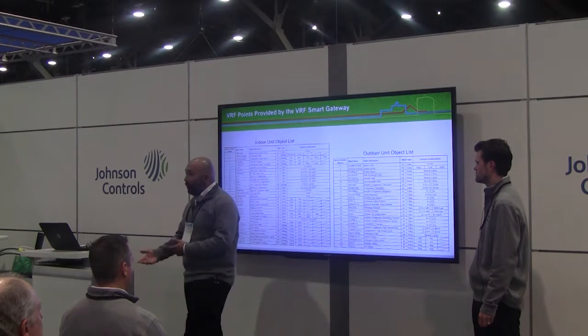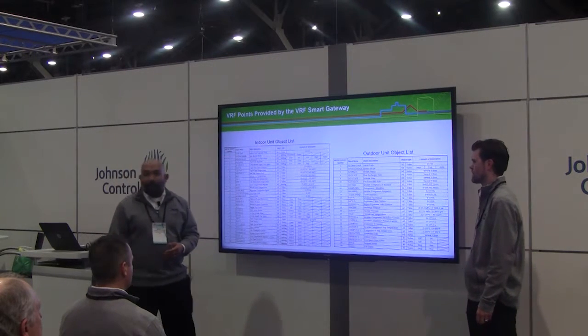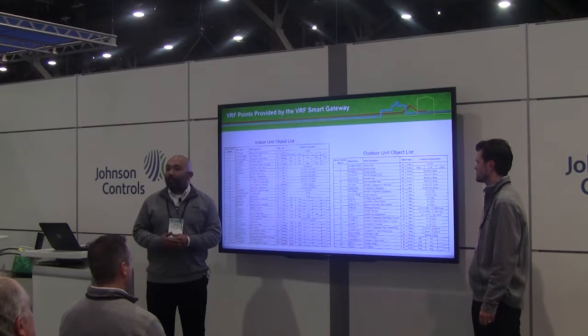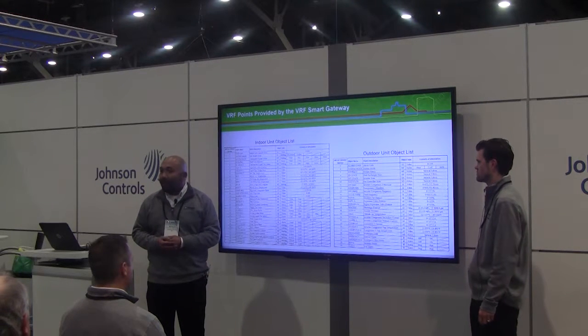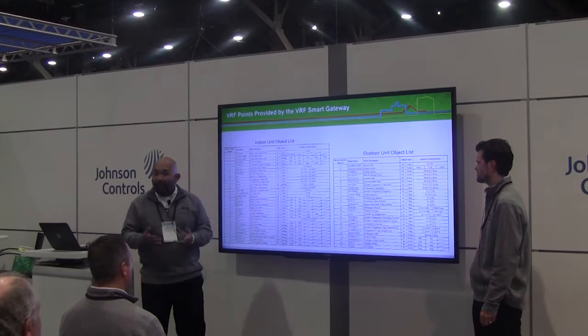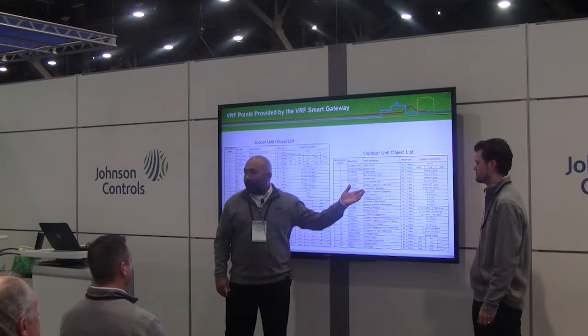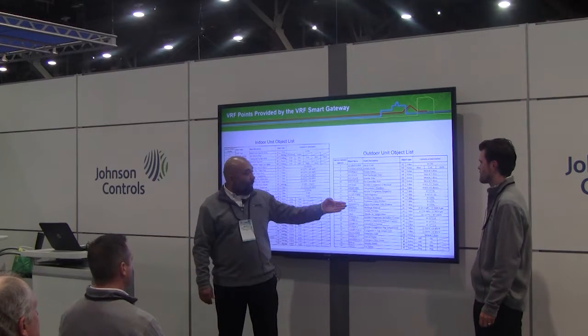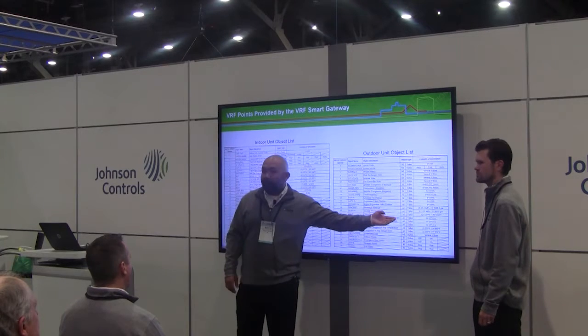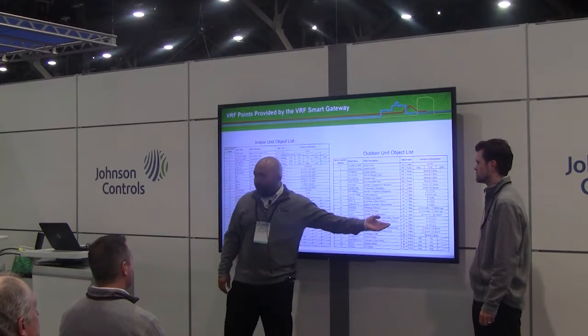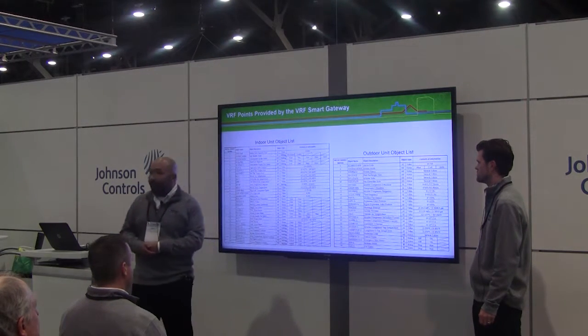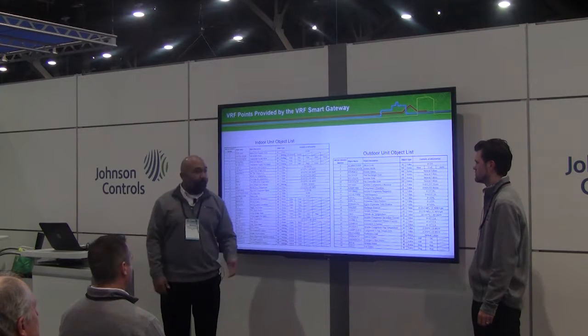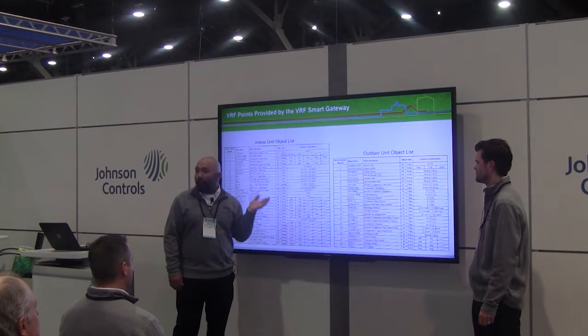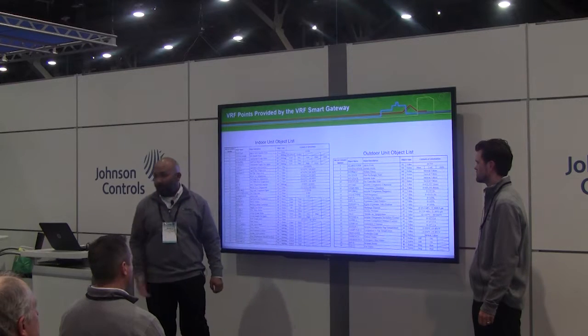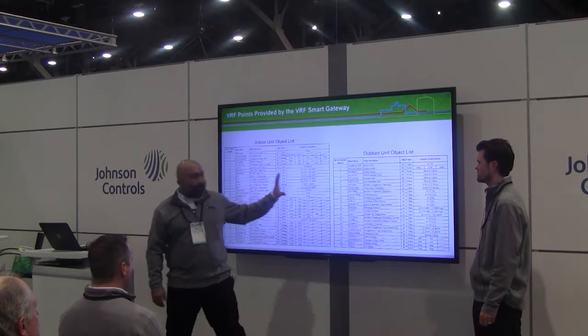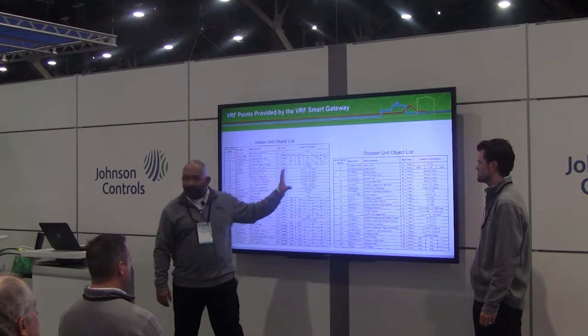On Metasys, we can trend all this information and go back to look at it six months down the line if our unit had a problem, and find that problem with this data. If discharge pressures start getting too high, we can diagnose based on that. We can tell if the coils are dirty, if evaporation temperatures are getting too low, or if our filters need changing. So having the most data available on the market is going to be your best bet.